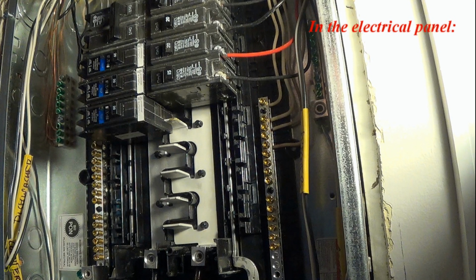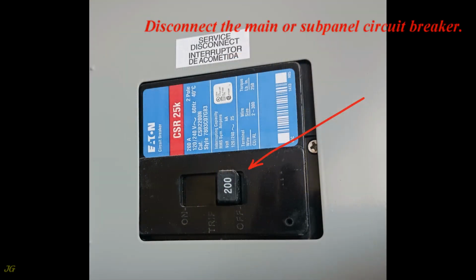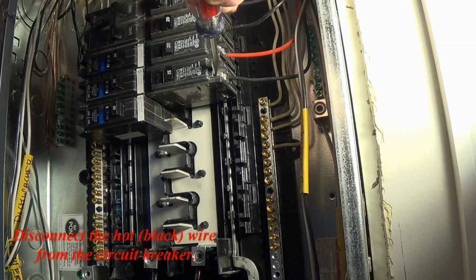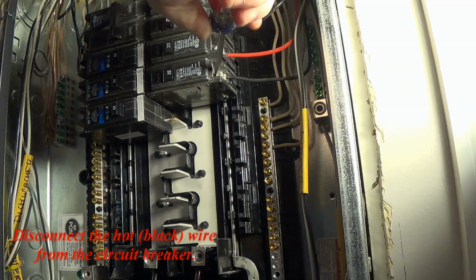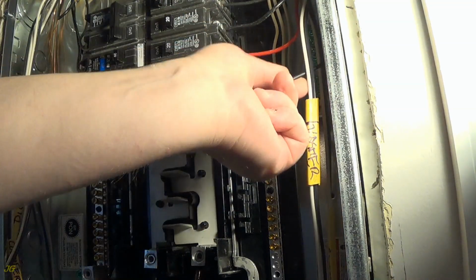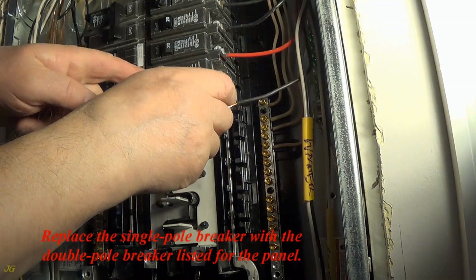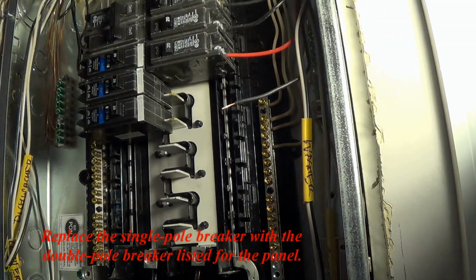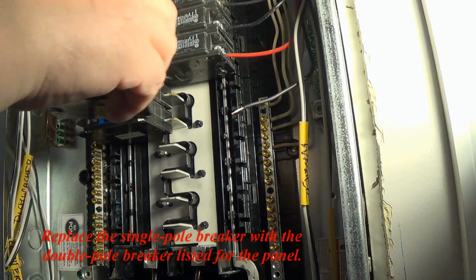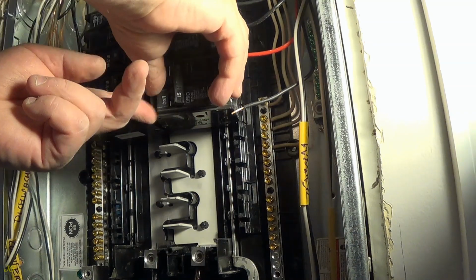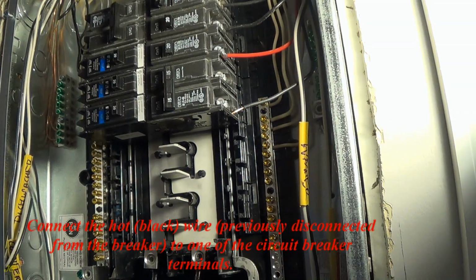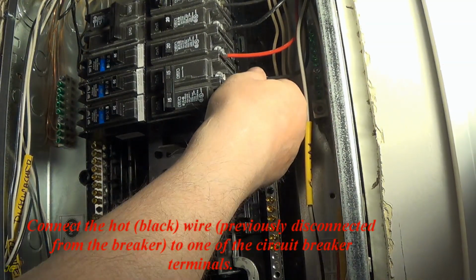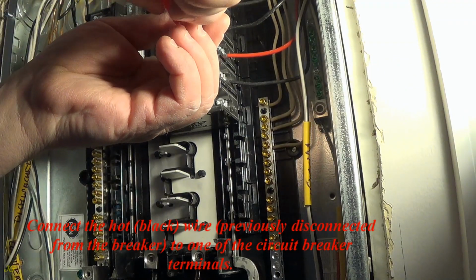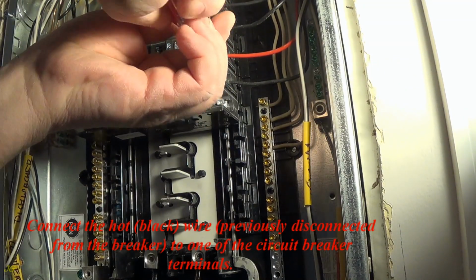In the electrical panel, disconnect the main or subpanel circuit breaker. Disconnect the hot, black, wire from the circuit breaker. Replace the single pole breaker with the double pole breaker listed for the panel. Connect the hot, black, wire, previously disconnected from the breaker, to one of the circuit breaker terminals.